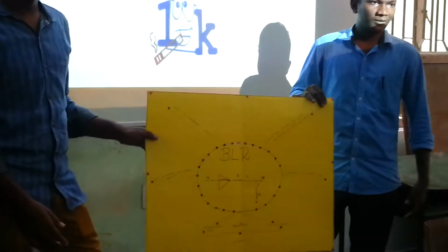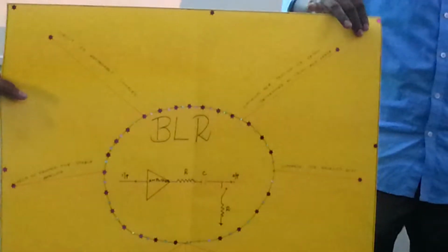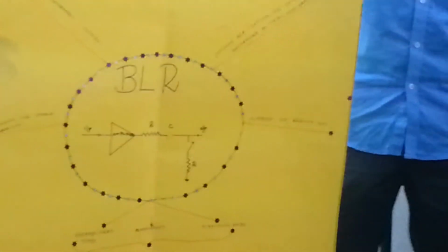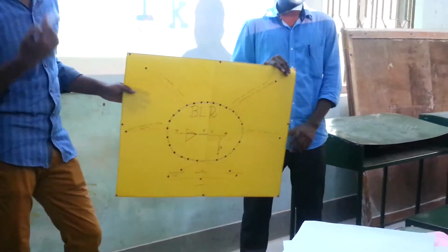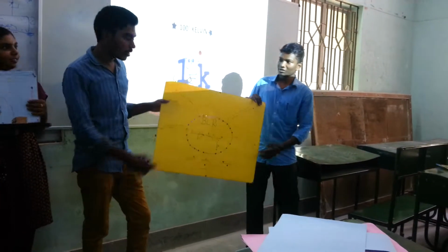Actually, it works as an automatic process for some amplifiers, but some of the amplifiers require controls to optimize the amplifier performance based upon the count rates and the preamplifier. So at that time it is not automatic. Actually, it will be set up based upon the trial and error method.